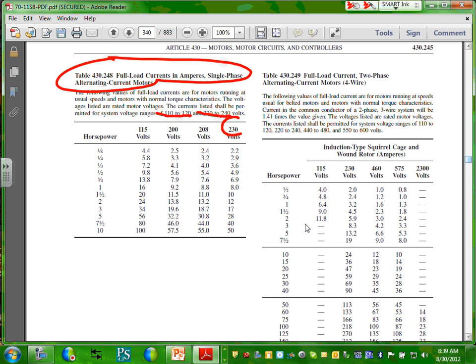So 240 goes usually with the closest, right? For motors, my friend, they rate the full load amp based on a lower voltage, because that's the worst scenario. So because my system is 240, I'm going to go to 230, right? This will go with 240 volt system. What's the horsepower? My horsepower is 3. What's the full load current at 3?